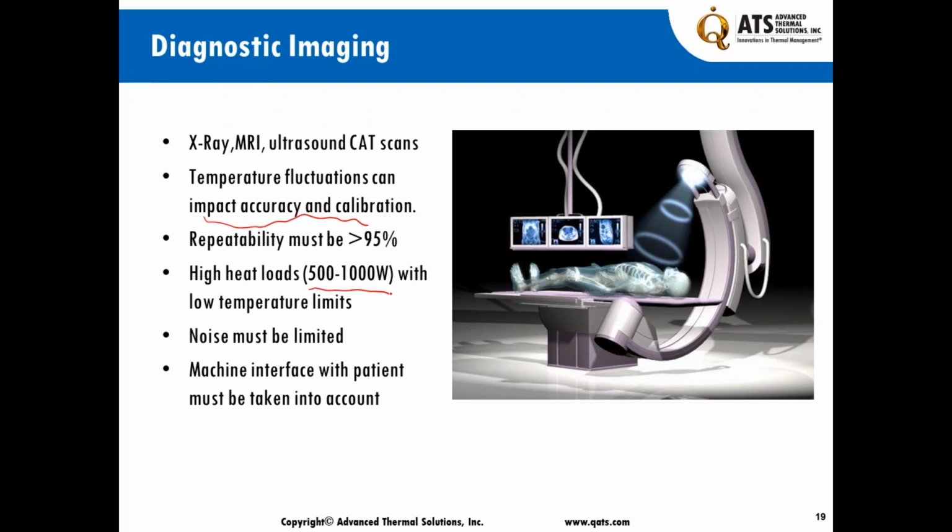And with low temperature limits, noise must be limited. A lot of patients get very agitated with this large equipment going around them, and they get claustrophobic or nervous. If any of you have had an MRI, I've done a couple of them, there's a constant pounding sound because of the magnets being charged and discharged, and that could be a point of concern for some patients. Machine interface with patients must be taken into account.